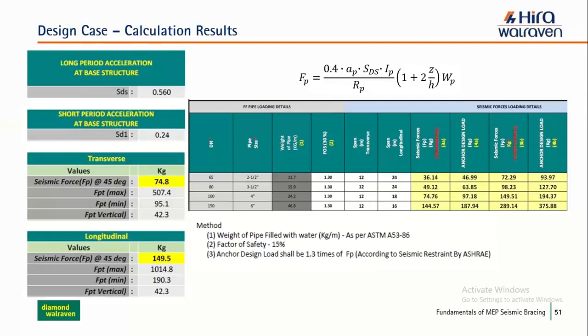Again the same thing for the first transverse, then longitudinal. It has a difference of span, and different spans are used for both. As per the standard, the transverse span should be different from the longitudinal, unless it is a four-way sway brace. And then here we have the pipe weight, factor of safety, and the anchor design shall be 1.3 times Fp.